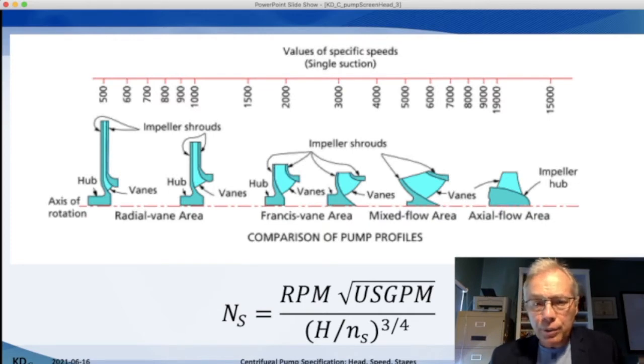The shape is quantified by the specific speed. This is the range of specific speeds for different types of impellers. Now the specific speed is a dimensionless ratio of pump speed, volumetric flow rate, and the pump head generated by the impeller.